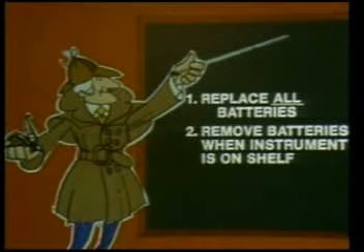First, when you replace batteries, you must replace all of them. There must be no partial replacement. Second, if the instrument is not going to be used for any length of time, the batteries must be removed. As you know, there really is no such thing as a leak-proof carbon battery.